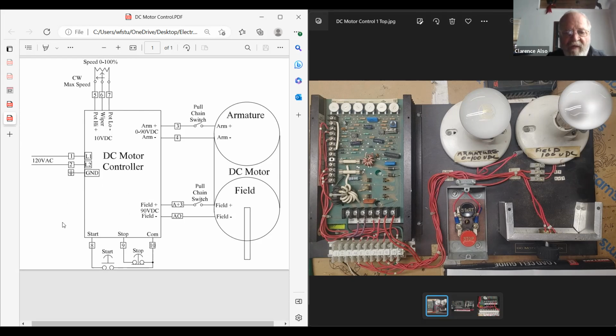That process of elimination points to the fact that we've got this start-stop switch here that maybe we haven't asked to start up. We could check things with voltages, but we don't know what the voltages are here - they didn't tell us that. We knew up here, so we could troubleshoot it. So maybe we'll do this with an ohm meter, since we can check to see if those switches work - a switch is like touching your ohm meter leads together or having them apart.